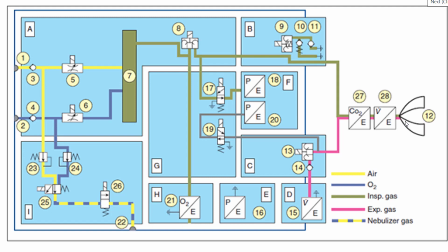They could also be powered by batteries, which are from 10 to 30 volts DC. Batteries are usually used to power ventilators that are used for home care and transport. So if you have a wall ventilator, you can't move it. If compressed air is being used for power, it will usually be sourced from tanks or from hospital outlets.